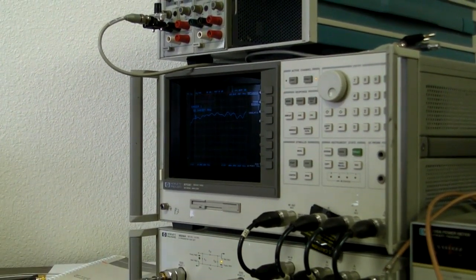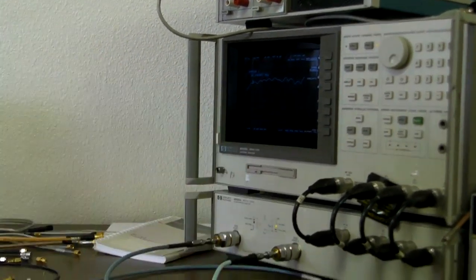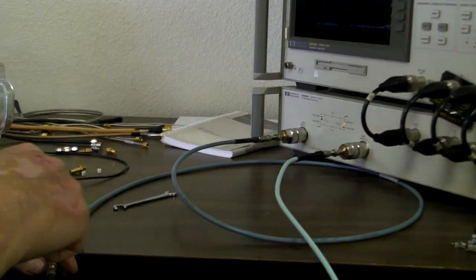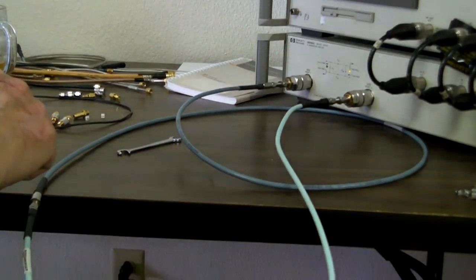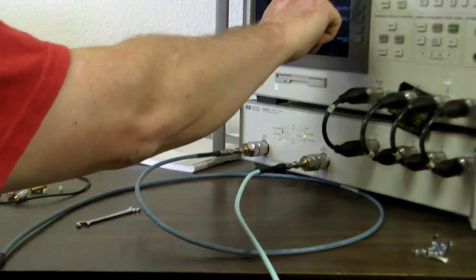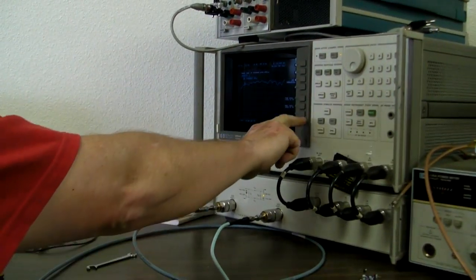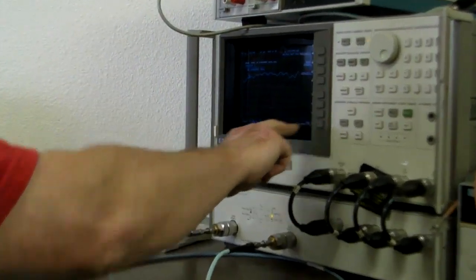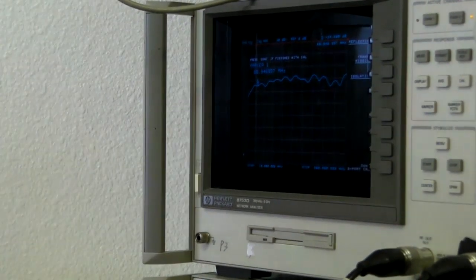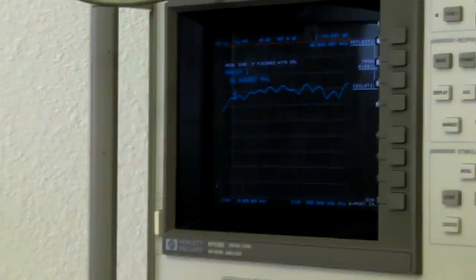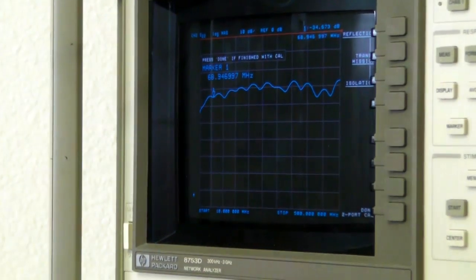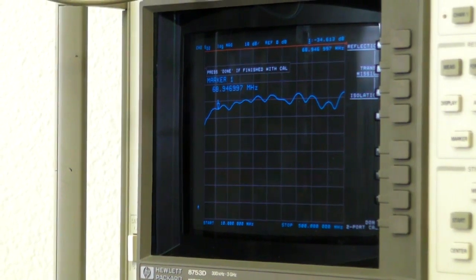So now it knows the reflection standard for both ports. It knows the through calibration for both ports. Since we're not going to do a really high-performance isolation measurement, we're going to tell it to omit the isolation terms and assume the instrument's perfect. This would only bother if we were doing like a duplexer where we wanted to see down to minus 100. We could take out the leakage terms of the instrument, which could be useful.